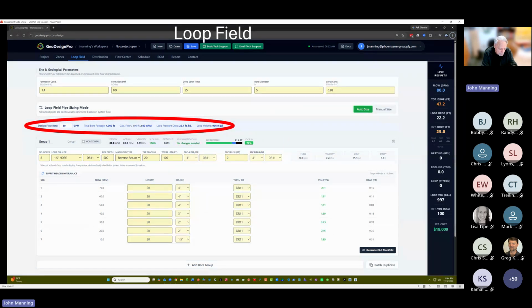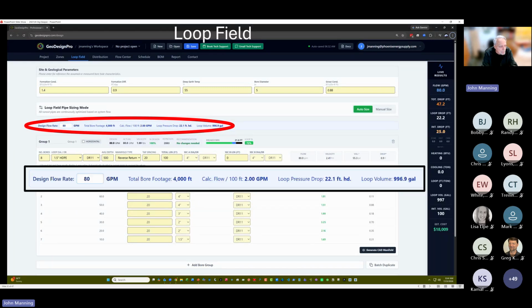There's additional information that is also updated live as you go through your design. And we'll blow that up so you can see it. You have your design flow rate, the total bore footage that's installed on your loop field. And then there's a parameter that I've used over the years as a guide of how many GPM per 100 foot of bore. And it turns out that if you're at 2 GPM, plus or minus a half, from 1.5 to 2.5 GPM per 100 foot is an indicator of whether or not that loop field is sized properly.